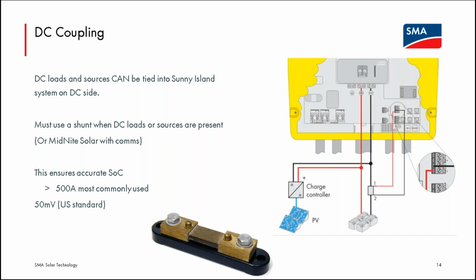The Sunny Island, almost everything that it does is driven by the state of charge of the battery bank. And if it begins to detect that the battery is behaving in such a way that its real state of charge is vastly different than what the Sunny Island is assuming or calculating, then it will shut the system down. So if something is loading the battery bank or recharging the battery bank and the Sunny Island doesn't know about it, very, very quickly the calculated state of charge and the actual state of charge will diverge, and the Sunny Island will shut the whole system down. So if anything is touching its battery bank besides it, it needs to know. Very, very smart machine, and it realizes if reality is different than what it calculates, it's not really safe to continue.